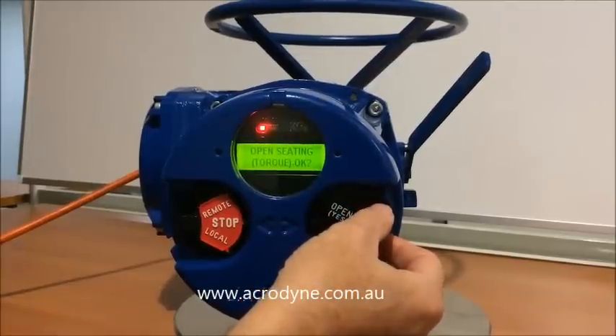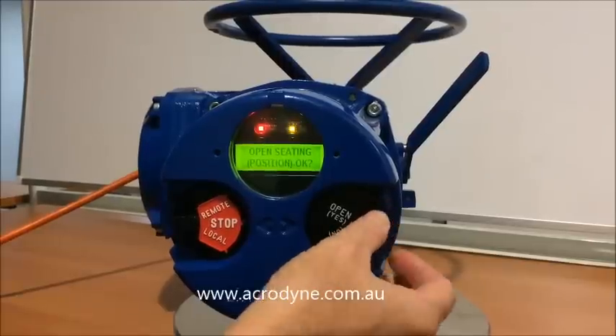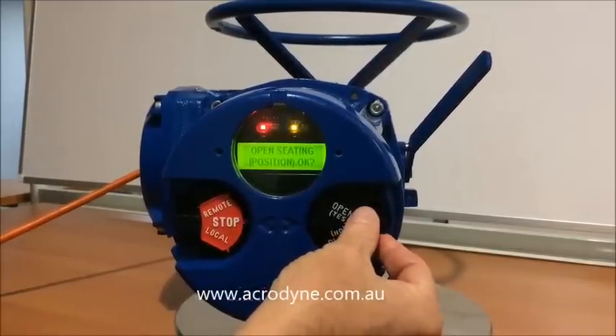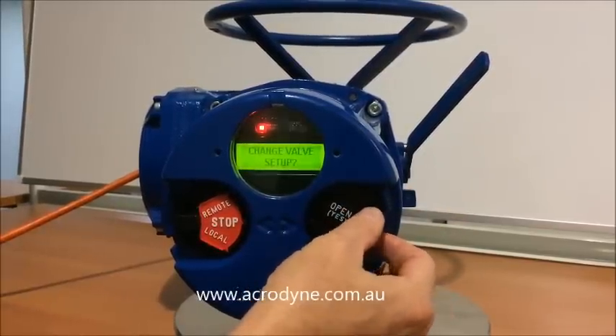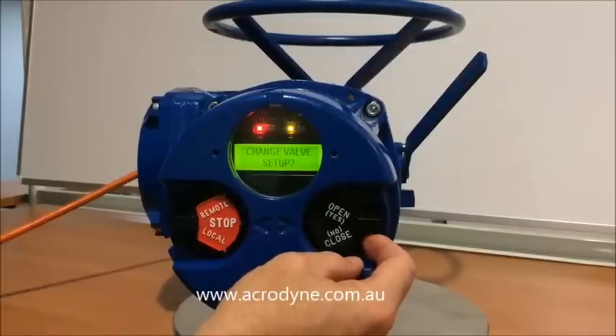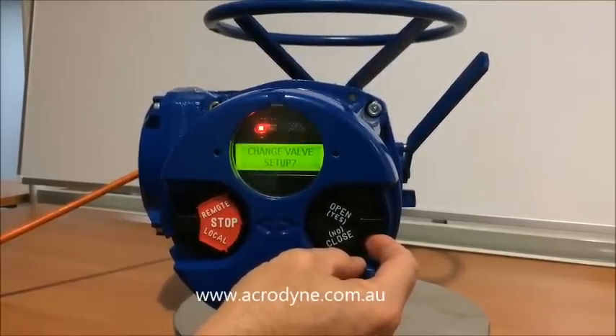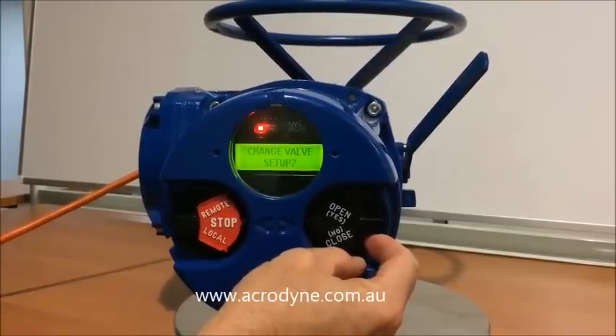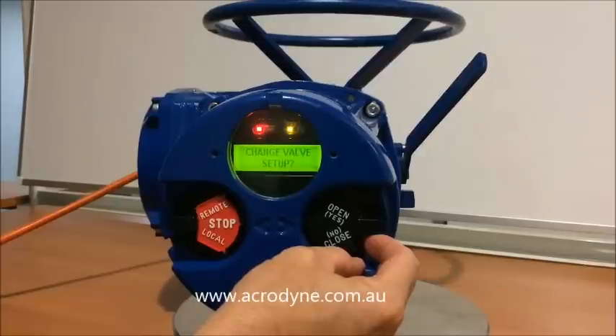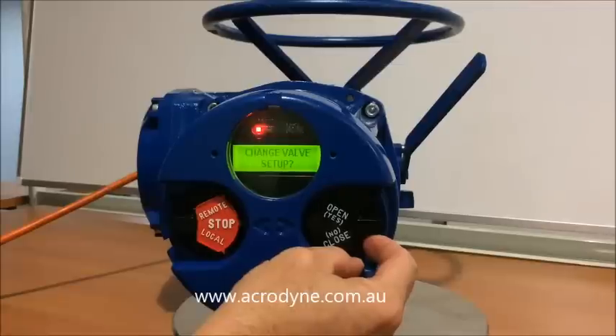We can also change the open seating to either torque or position. In this case we'll agree to position, say yes to that. And you do have to be very careful in this area. A common effect would be a butterfly valve over-travelling because it hasn't hit an end stop because we have it on torque, not position.